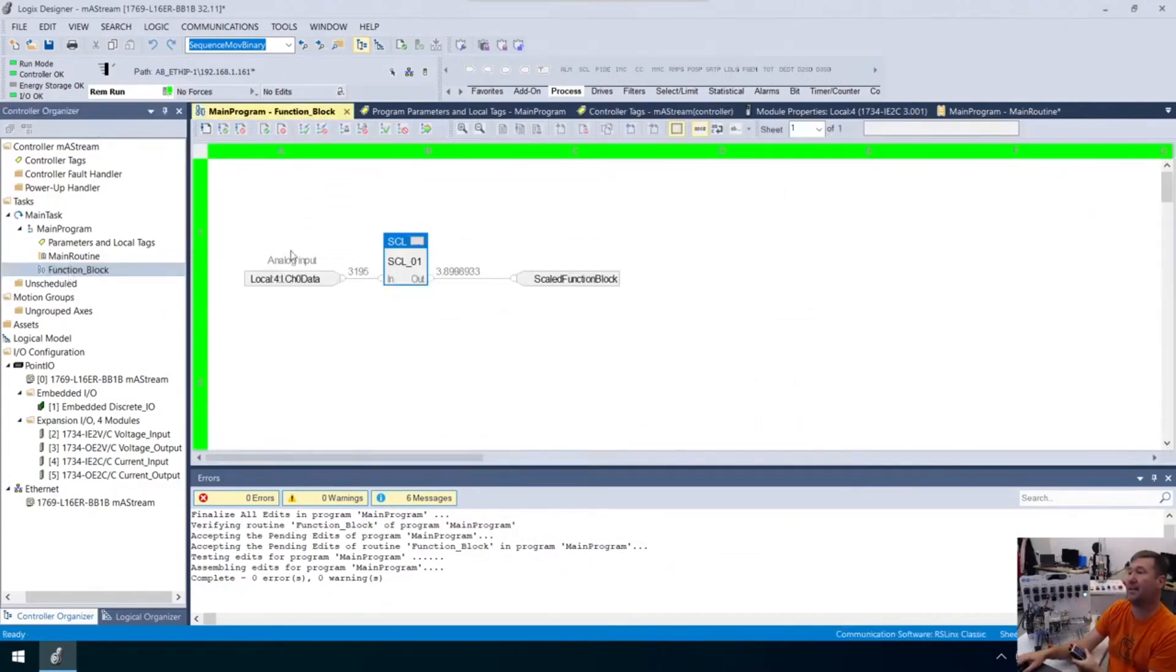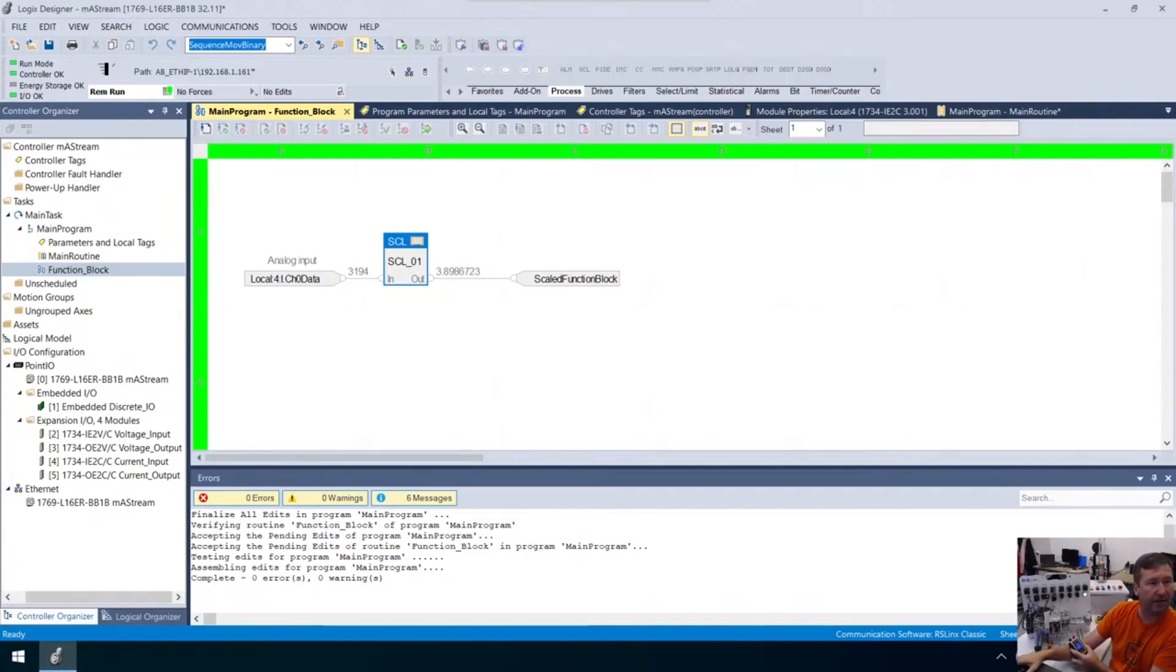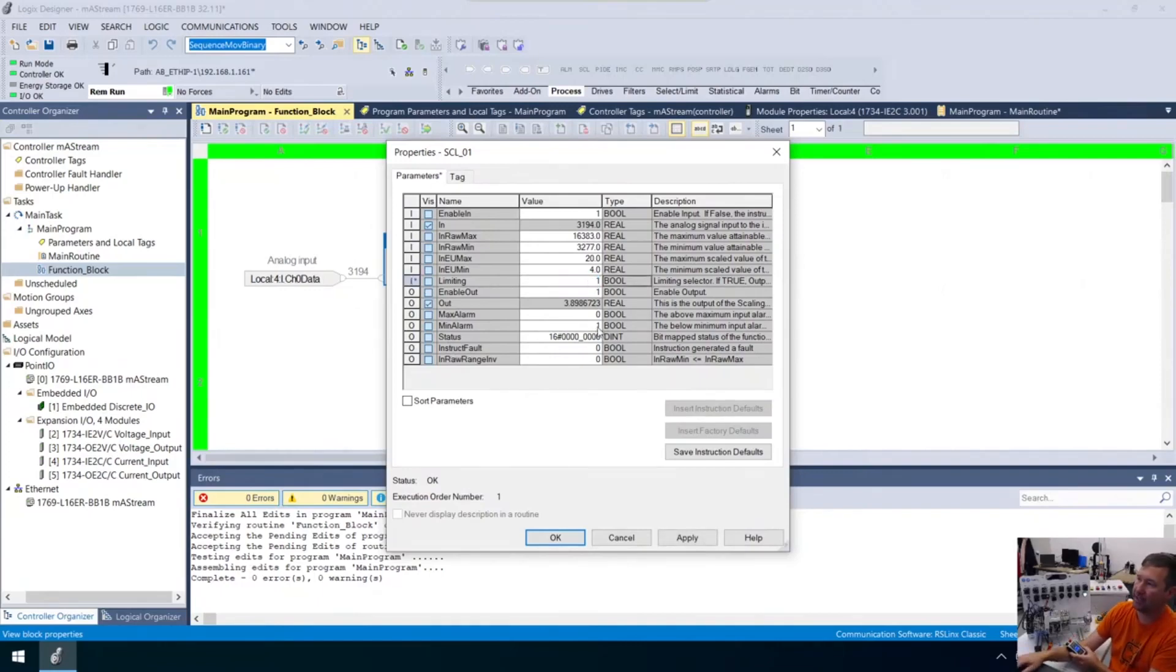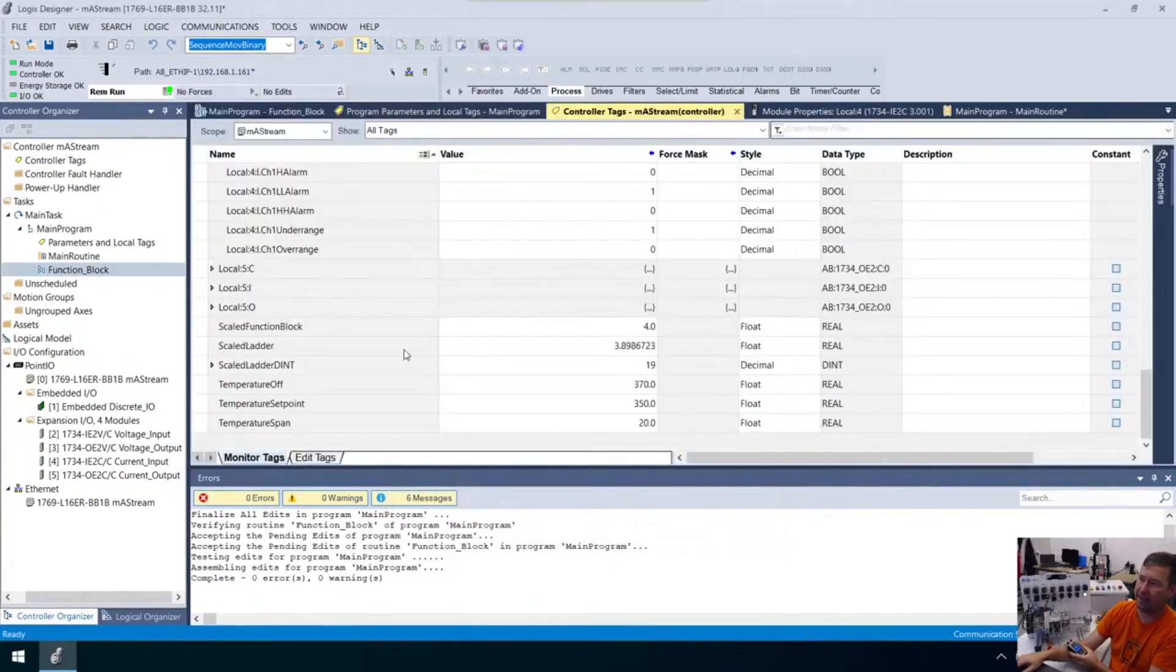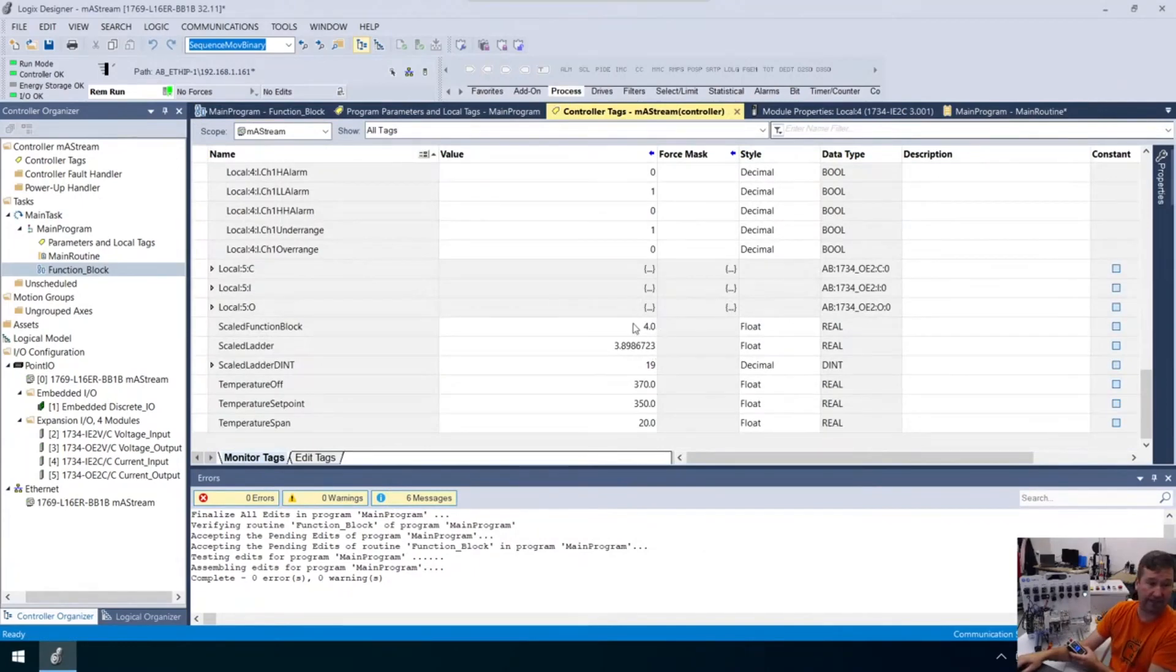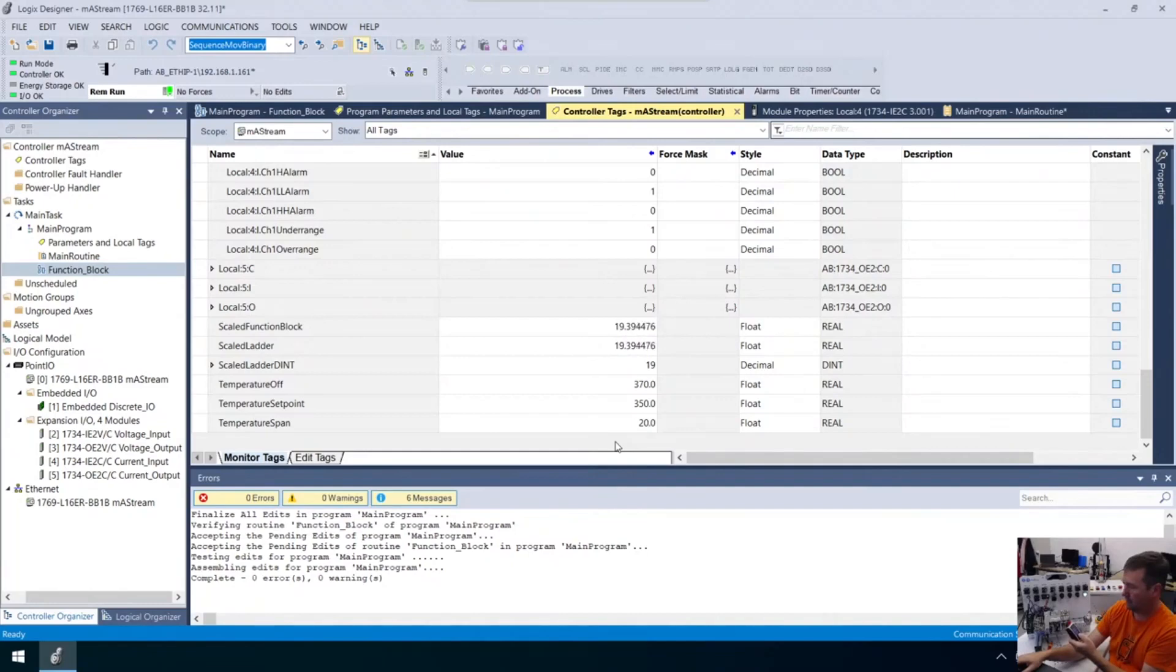Somebody was asking what does it mean if your value goes negative? If you have that problem and you're like I just wish it quit doing it, we have this limiting right here. We can change that to a one and hit apply. Notice now our value is four. Our real value is 3.896, but as a function block it's going to limit it to four. Now I bump it up and we're going to line up together.